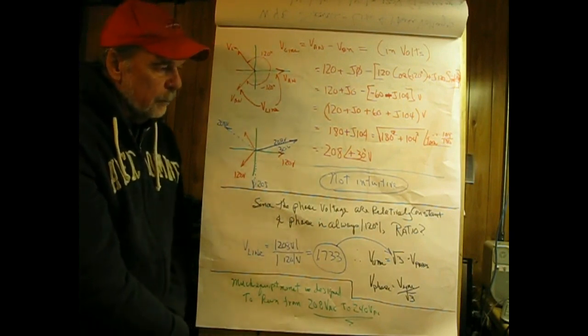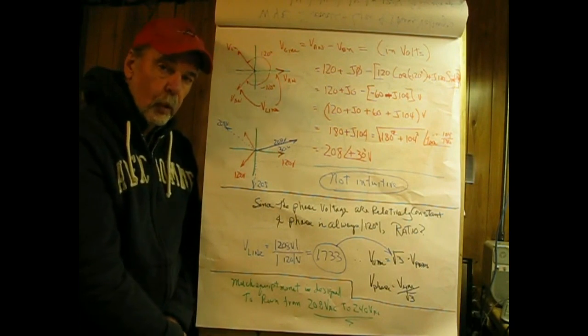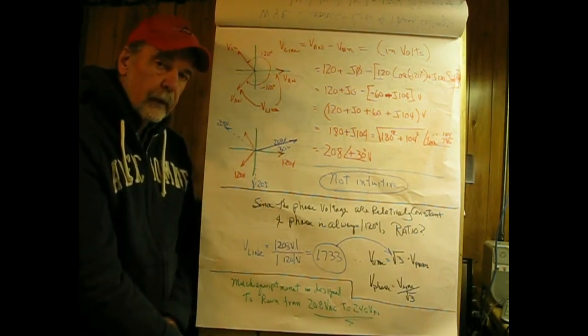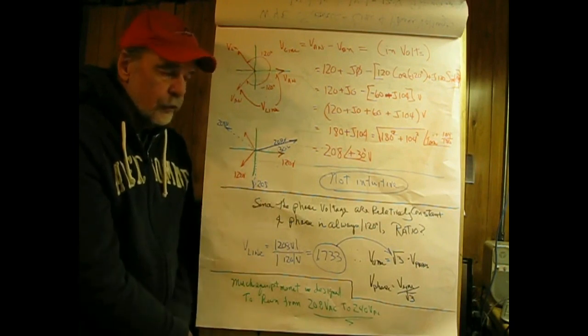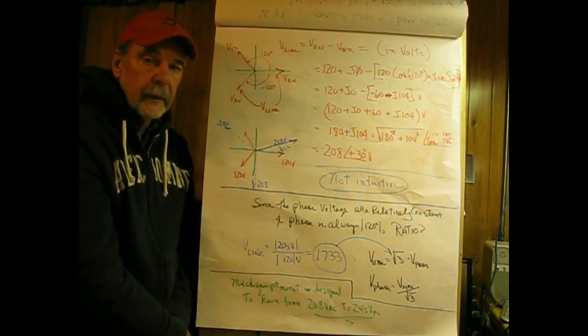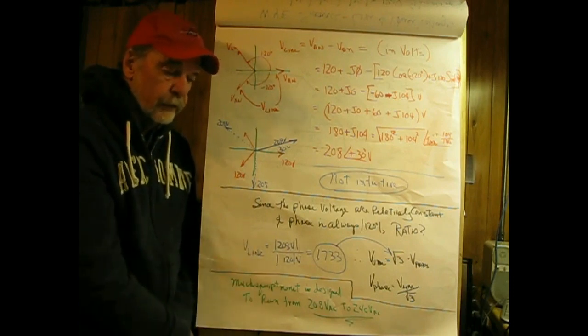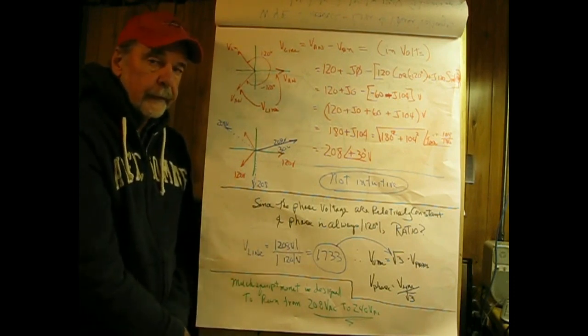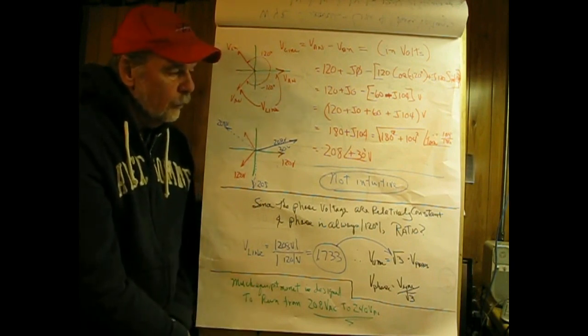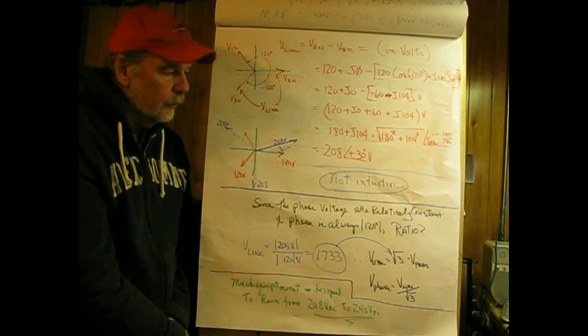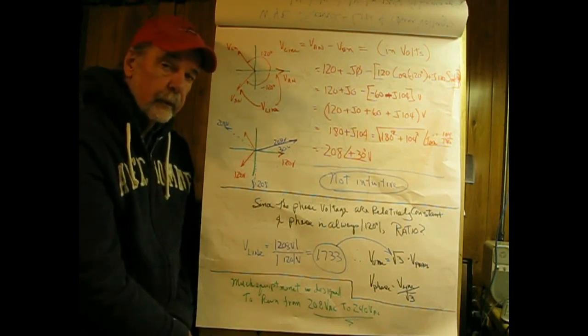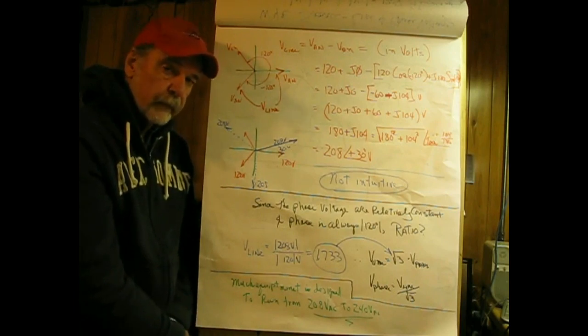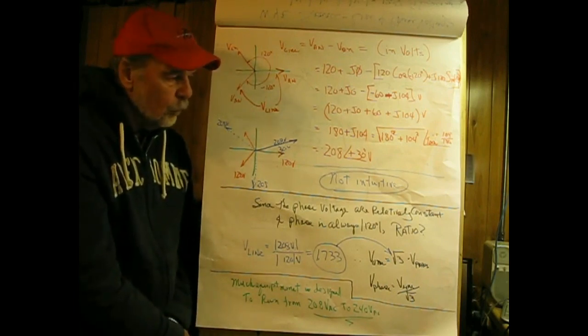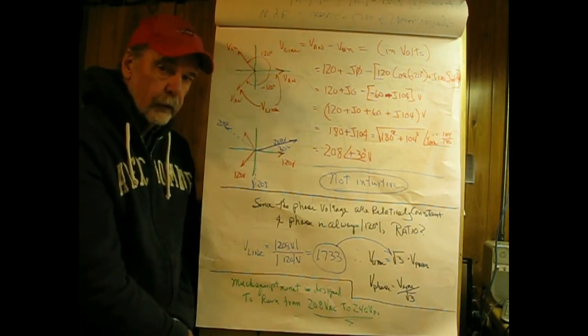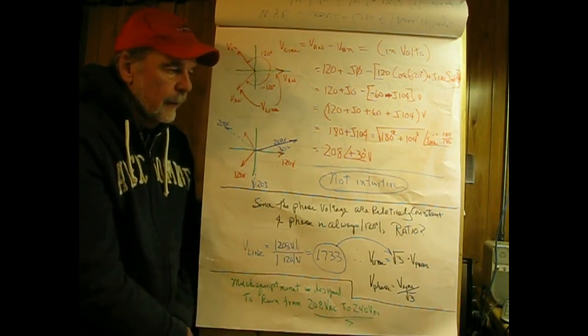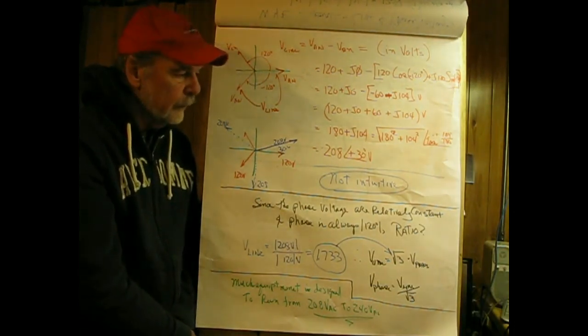A lot of appliances are built to run between 208 and 240 volts. Some places, like the church I attend, have 208 coming in, used for the French fryers and fish fryers in the kitchen. It used to be 240, but the incoming line was smoking, so it was upgraded to three-phase. With 208 coming in, it just takes a little longer to heat up the grease in a French fryer, but as long as it can keep up, it'll work fine.